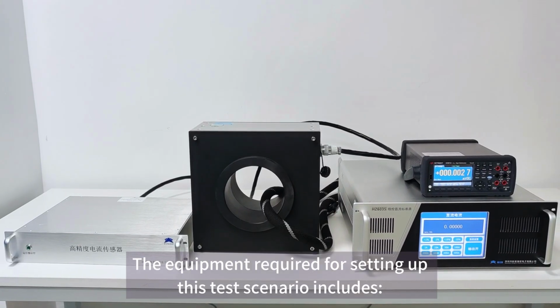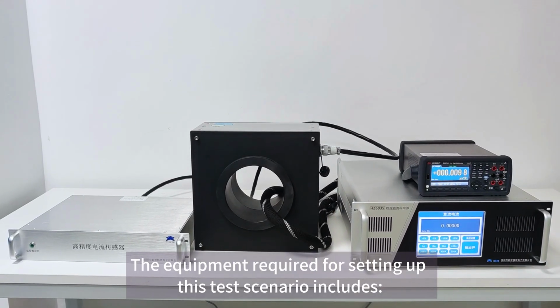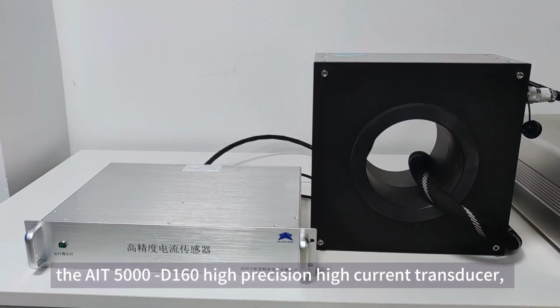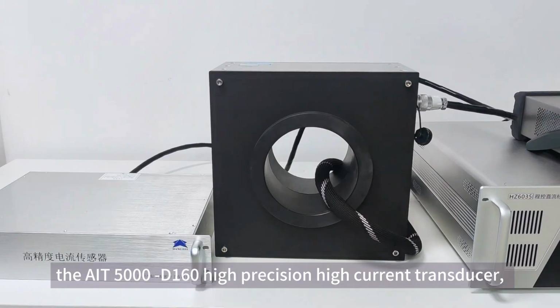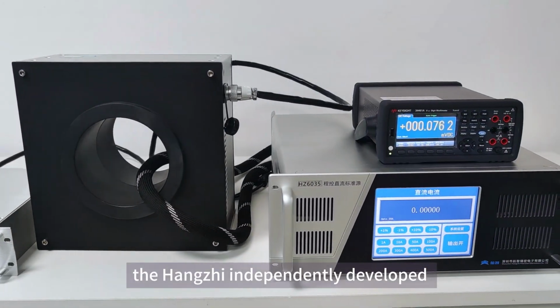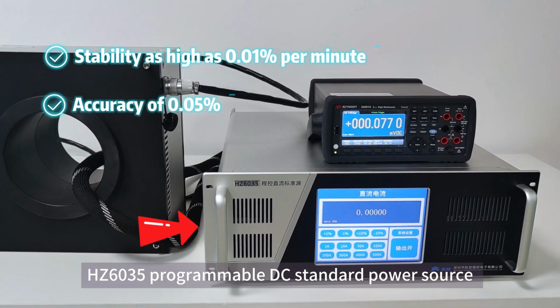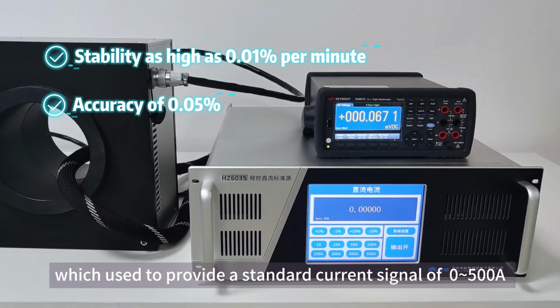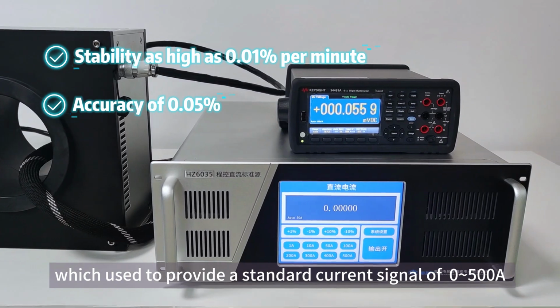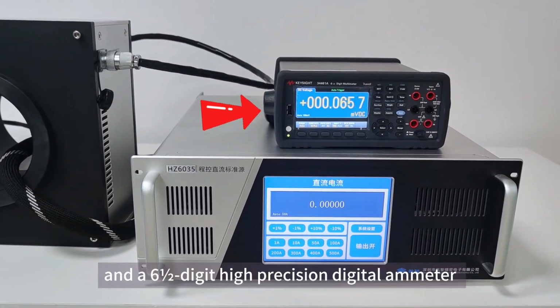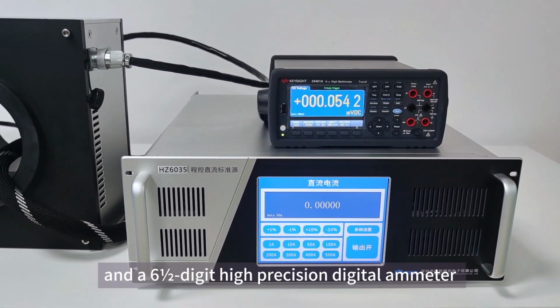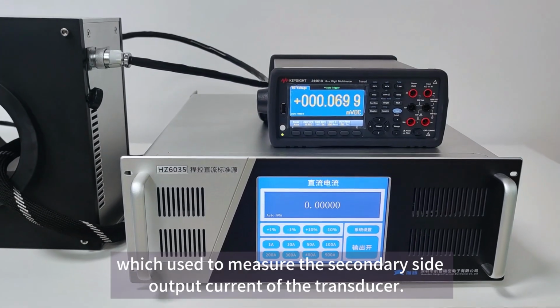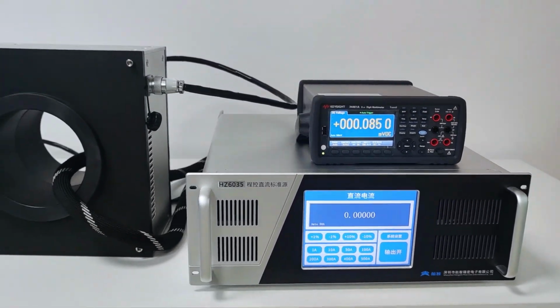The equipment required for setting up this test scenario includes the ait5000 D160 high-precision high-current transducer, the Hangzhi independently developed HZ6035 programmable DC standard power source, which is used to provide a standard current signal of 0 to 500 A, and a 6-digit high-precision digital ammeter, which is used to measure the secondary side output current of the transducer.